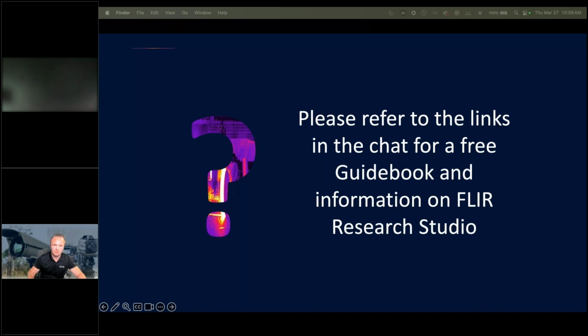And then you can send it back to us, and if you want, we can give you an as received and as left calibration on the recal, so you can make sure that it was still in cal when we received it and see what the new data is when we shipped it back out to you. If you're doing your user calibration, then by definition, you have all the hardware on site to verify if the camera is still accurate or not, so you can decide what your validity is on that.